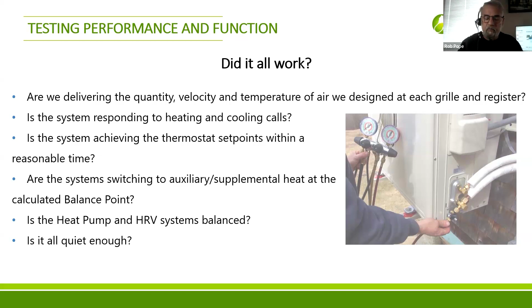Are we delivering the quantity, velocity, and temperature of air we designed at each grill? Is the system responding to heating and cooling calls? Is the system achieving the thermostat set points within a reasonable time? These are things we're checking, remember. Are the systems switching to auxiliary supplemental heat at the calculated balance point, when we need it, not before we need it? Is the system balanced, especially the HRV, if there's an HRV involved? And of course, is it all quiet enough? Are there noises that shouldn't be there, like airflow sounds? If we've got blocked registers or pipes or something, we have air screaming out of a single grill, what's going on there. Rattling, anything outside of what we would expect.